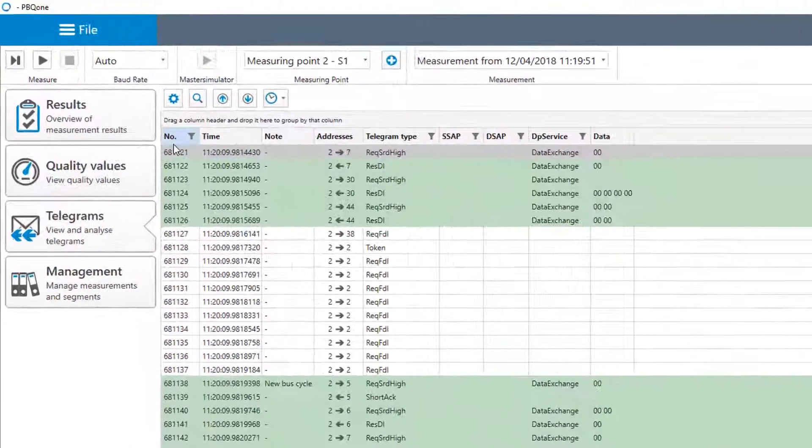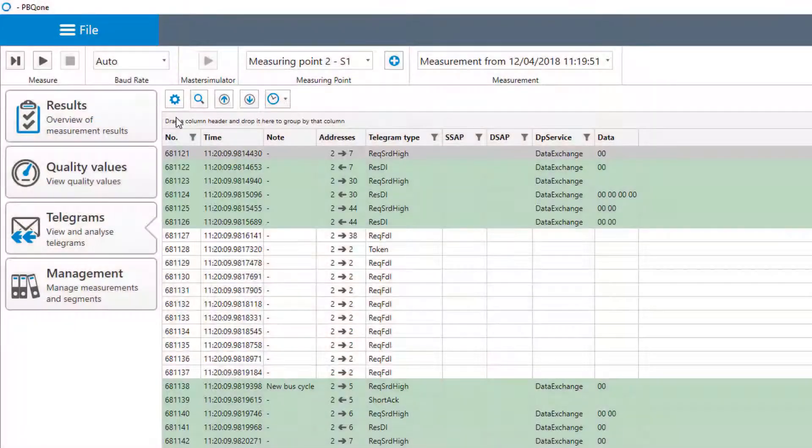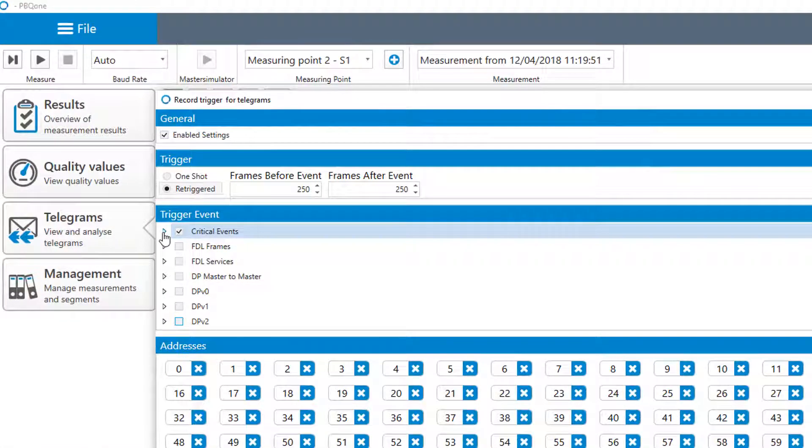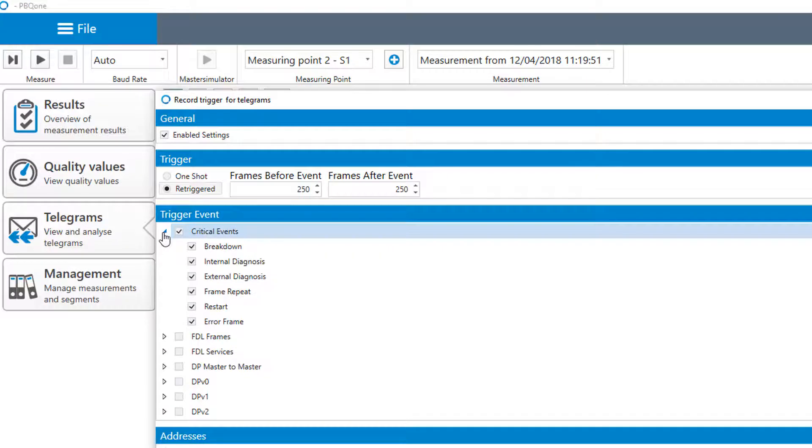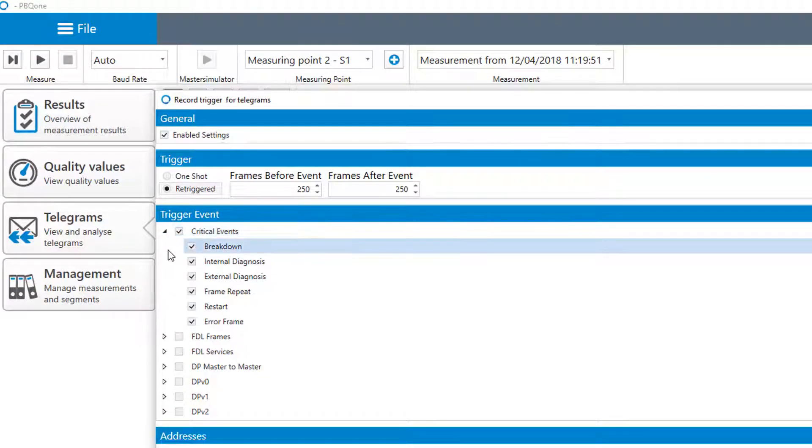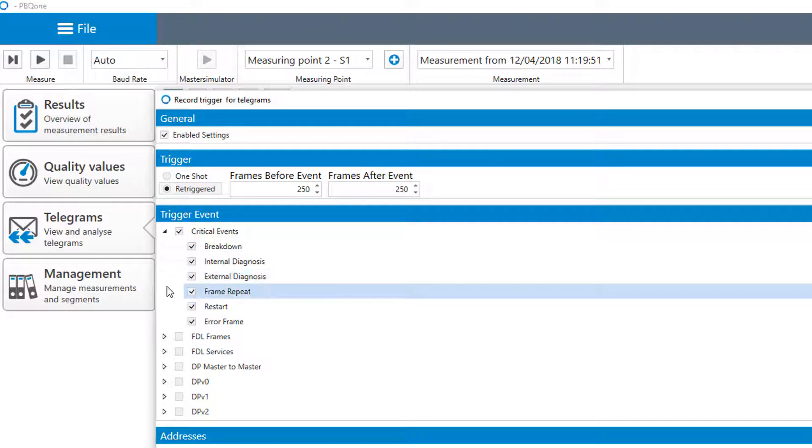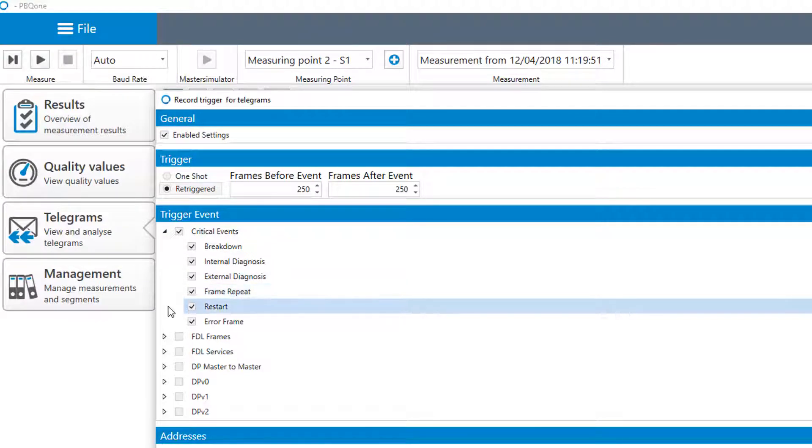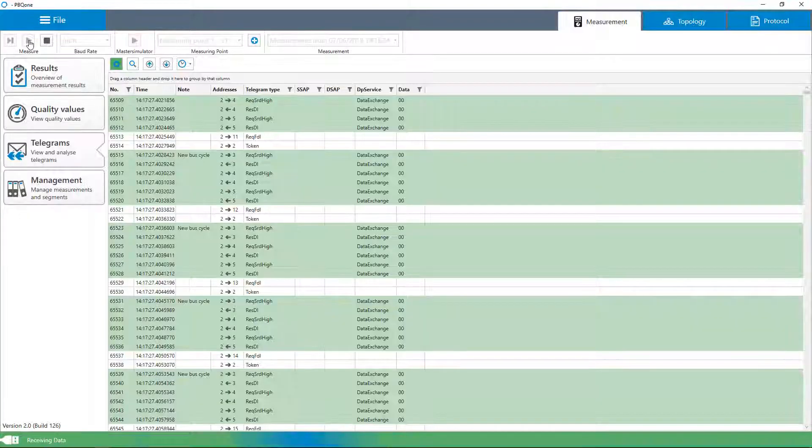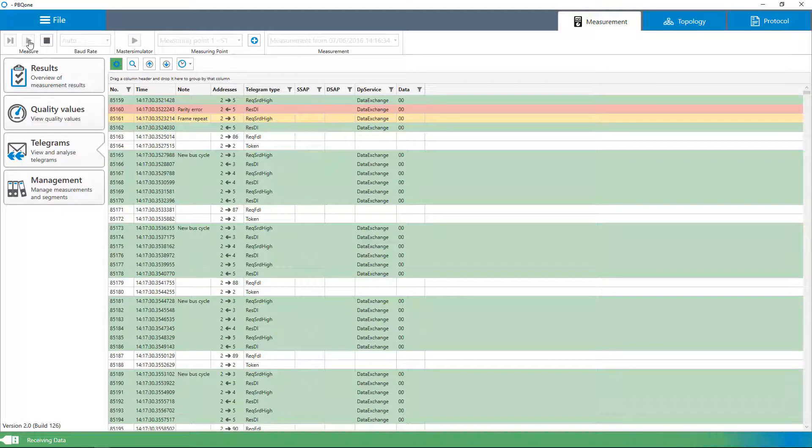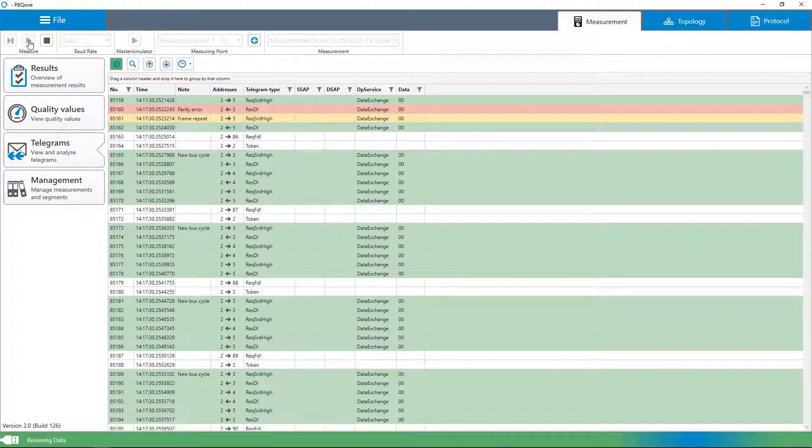By setting special recording triggers, it is possible to display individually selected events such as error telegrams, telegram repetitions, diagnosis and failures for targeted real-time monitoring. These events are easy to identify by their background color and are also displayed in plain text.